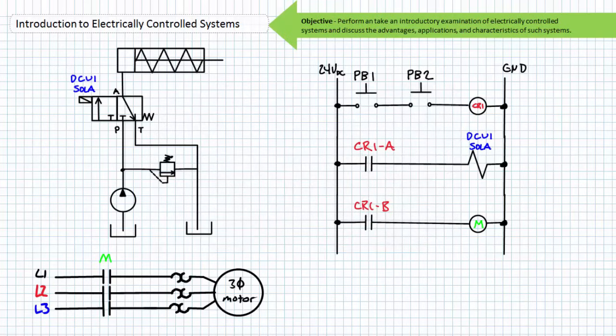Pressure, flow, voltage, and current ratings at various points within our system should be able to identify the source of our problems. Another great technique for practicing troubleshooting scenarios is to mentally insert an error into our system. If you really understand this system, you should be able to predict how the system will react. Consider a broken wire in the second rung of our ladder logic diagram.